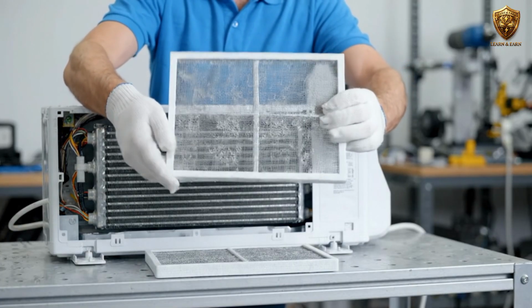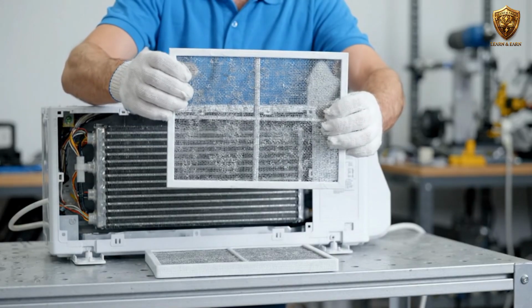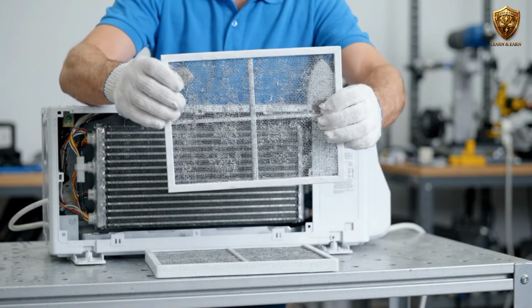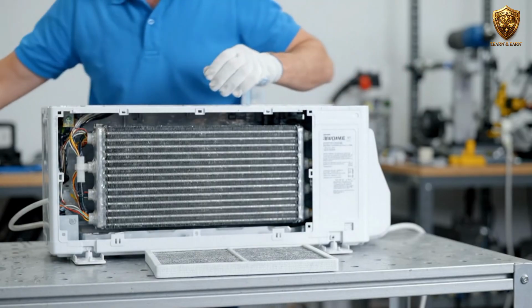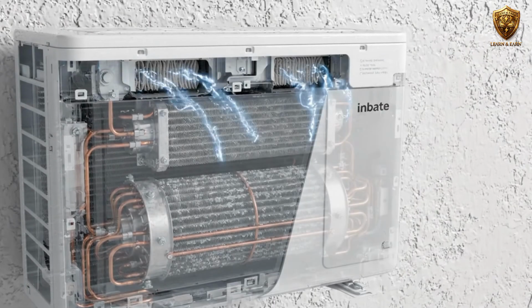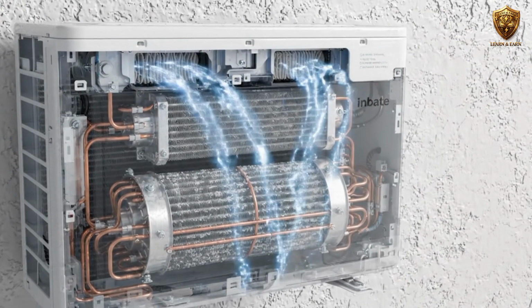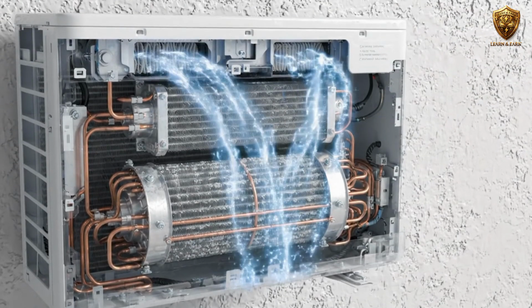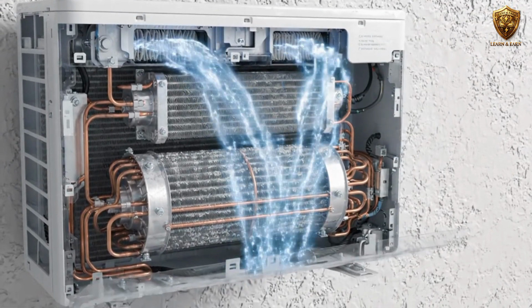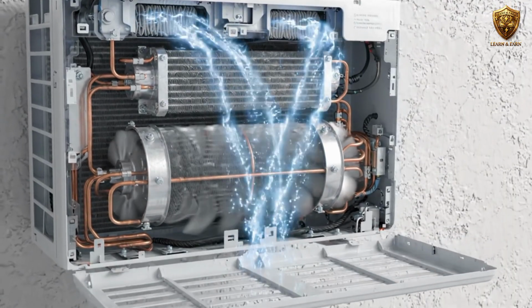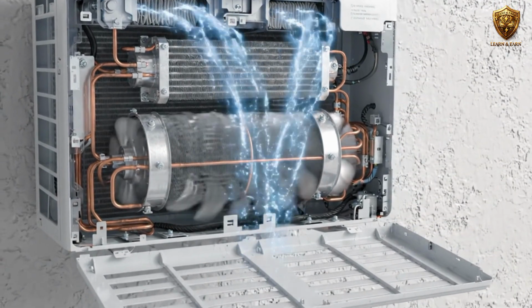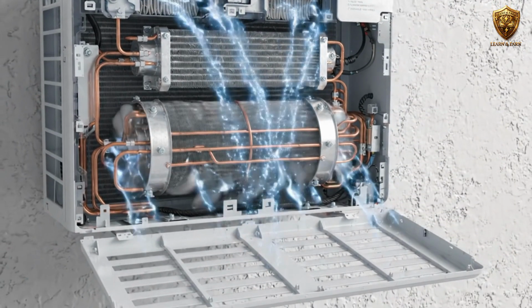The evaporator coil can become dirty, the blower can collect dust, the blower motor can have a problem, or the duct system can restrict the air. Look at the supply airflow and compare it with what the system normally produces. If airflow is weak at several supply outlets, the problem may be closer to the indoor unit or duct system. If one outlet is weak while others are normal, the restriction may be local.